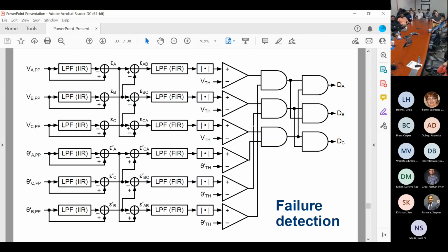Okay, so here's the thinking. The thinking is we want to get rid of common mode things. So for example, if all three phases went low then high, probably not the A phase fuse failing, right? It's probably some transient that flew through the power system. So that's the intent of it, you don't expect all three. Now, there could be some common mode thing in the sensor that makes all three fail at once. But you kind of think, hey, one's going to fail or another going to fail. So it gets rid of anything that all three see.